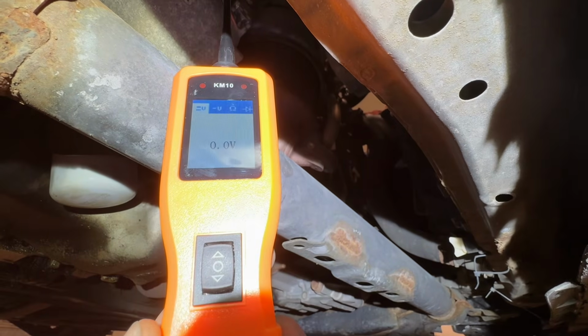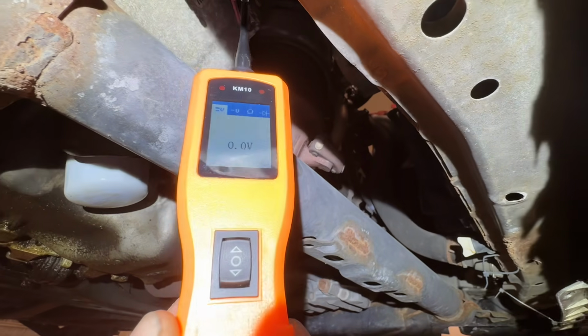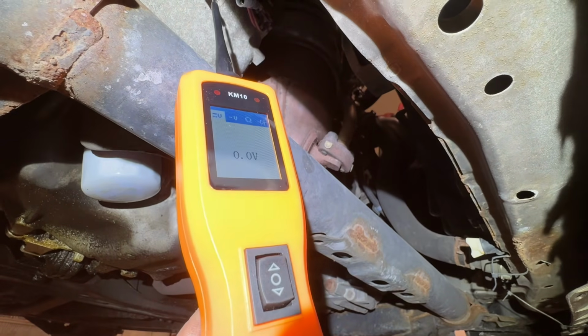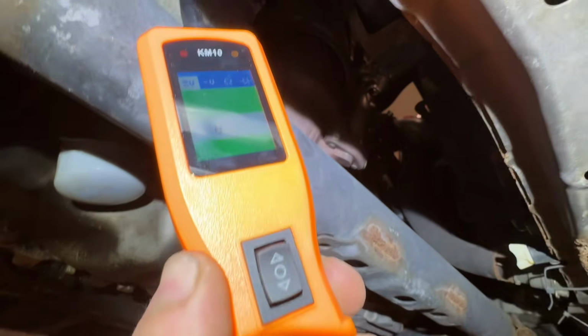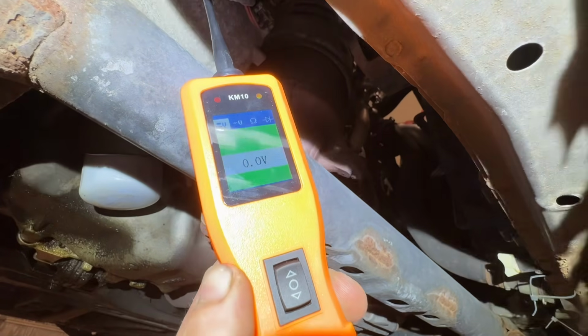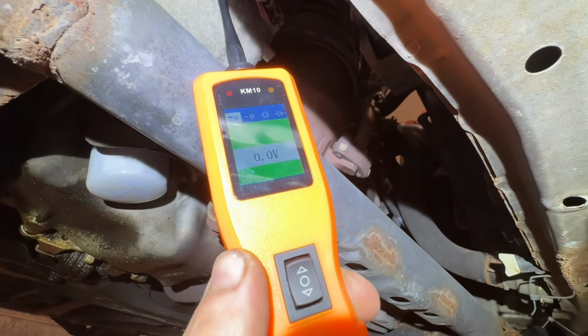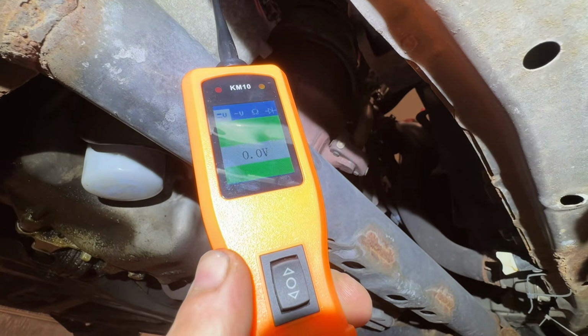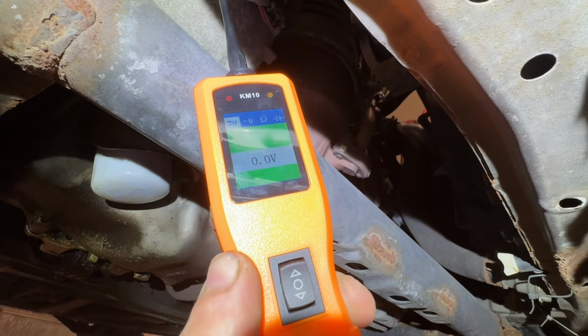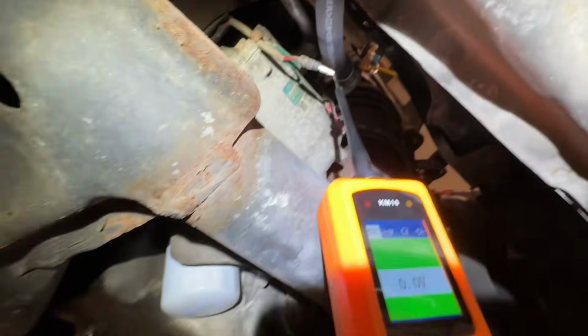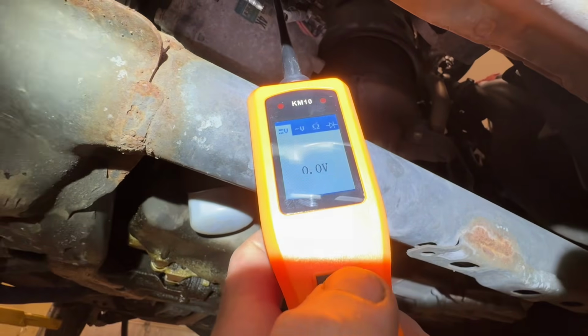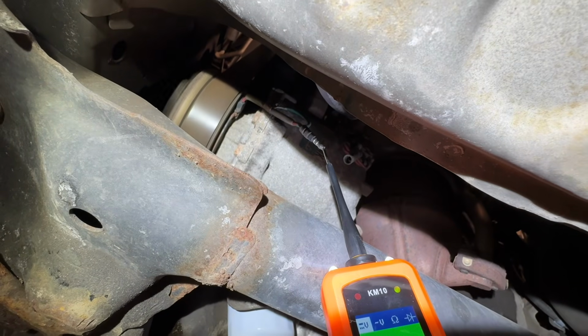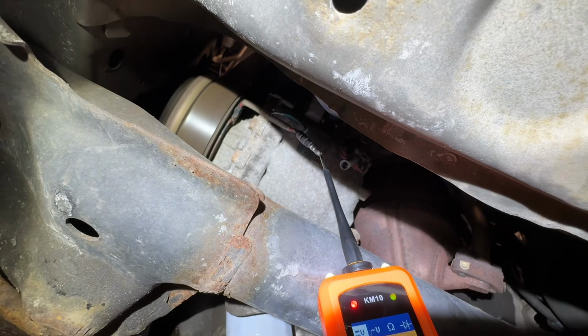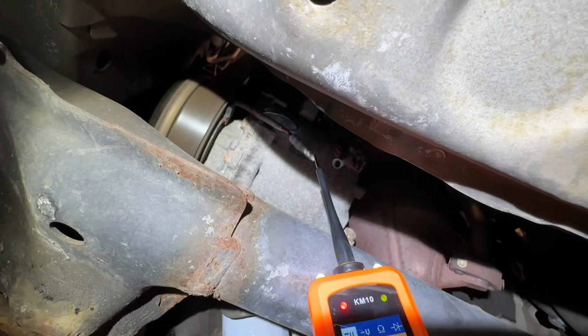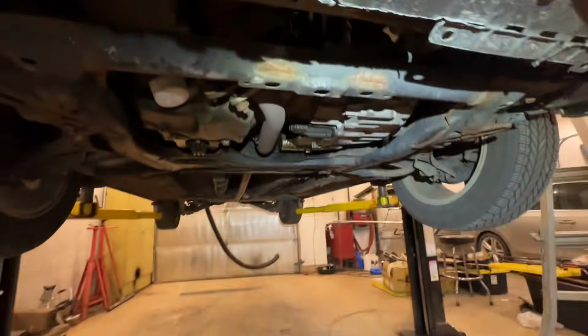And we're going to feed it right in there. As you can see, we've got 0 volts coming out of that connector. So the next thing we'll do is go to this connector. We've also got 0 volts, and it's showing ground, probably with a bit of resistance, because it's going to ground through the clutch. So now I'm going to apply 12 volts to it by pressing the up arrow. And look at that, the compressor kicks on immediately. So that tells me the compressor's good. It actually sounds quite good too.